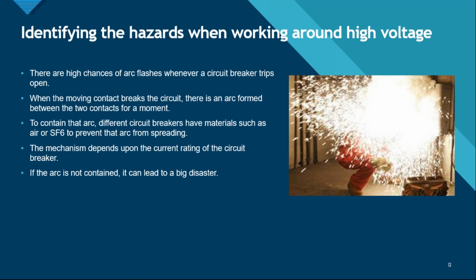All right, identifying the hazards. There are high chances of arc flashes whenever a circuit breaker trips open. Basically, a circuit breaker is a switch. It has a fixed contact and a moving contact. So whenever the circuit breaker receives a tripping command, the moving contact moves, it breaks the connection, and the circuit is broken. But when the moving contact moves, an arc is developed between the two contacts for a fraction of a second. If that arc is not contained, there are high chances of arc flashes happening around circuit breakers.